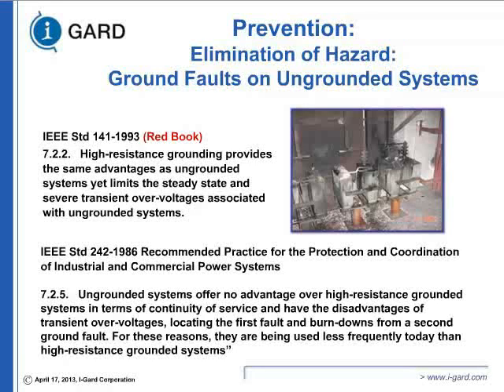IEEE Standard 242 tells you an ungrounded system offers no advantage over a high resistance grounding system. The advantage you have in a delta, ungrounded system, the first fault not shutting it down, is still available in a high resistance grounding system. You can continue the operation, but one of the disadvantages in a delta system is the transient voltage, which is removed in high resistance grounding.